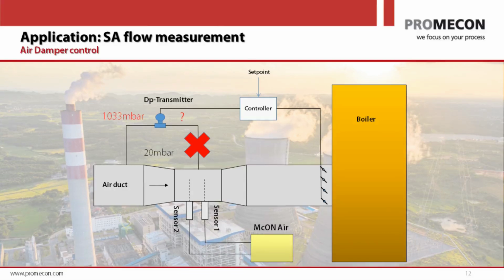And if that happens, nobody in the control room notices that. And I will explain in a minute why that is such a problem. But let's first look at the primary effect. The primary effect is that your dP transmitter is not measuring dP anymore. dP stands for delta pressure. And it's very important that the two impulse lines are both open because you only want to measure the delta, so the difference between one leg and the other one.